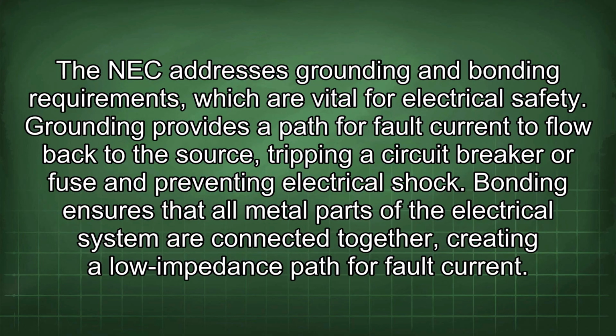The NEC addresses grounding and bonding requirements, which are vital for electrical safety. Grounding provides a path for fault current to flow back to the source, tripping a circuit breaker or fuse and preventing electrical shock. Bonding ensures that all metal parts of the electrical system are connected together, creating a low impedance path for fault current.